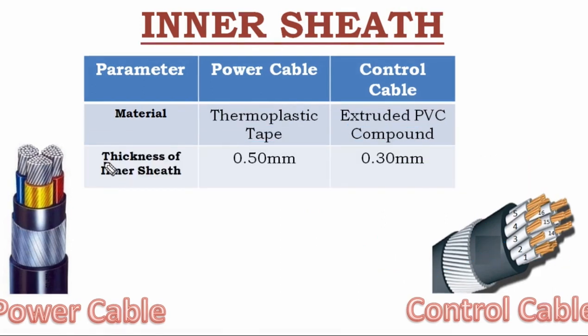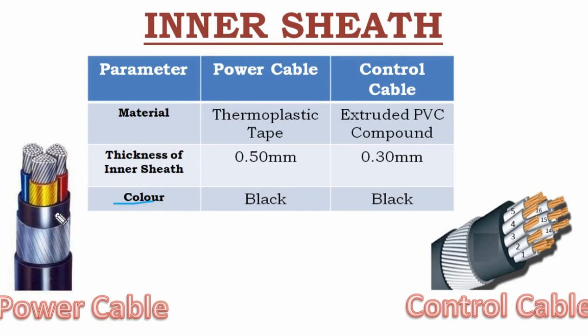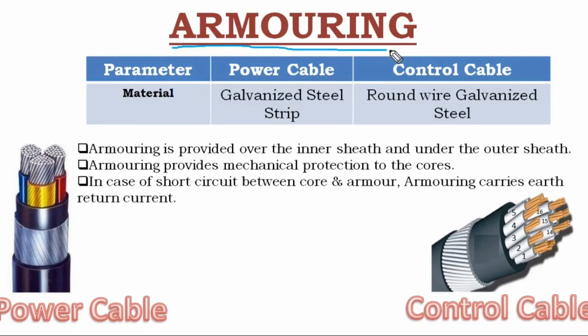The second parameter of the inner sheath is its thickness. In the power cable, the thickness of the inner sheath is 0.5 mm, and in the control cable it is 0.30 mm. The third parameter is color — the inner sheath color is black for both the power cable and the control cable.